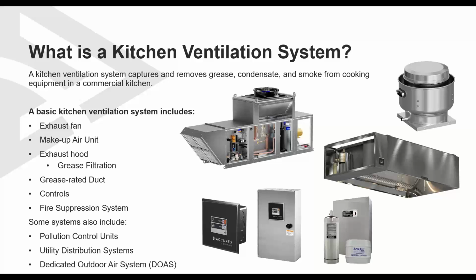So what is a kitchen ventilation system? It is not just the hood that you see in the commercial restaurant. A ventilation system also includes an exhaust fan, makeup air unit, exhaust hood with grease filtration when required, grease-rated ductwork when required, controls of some sort, and a fire suppression system when required. Some other systems may include pollution control units, utility distribution systems, and dedicated outdoor air systems.